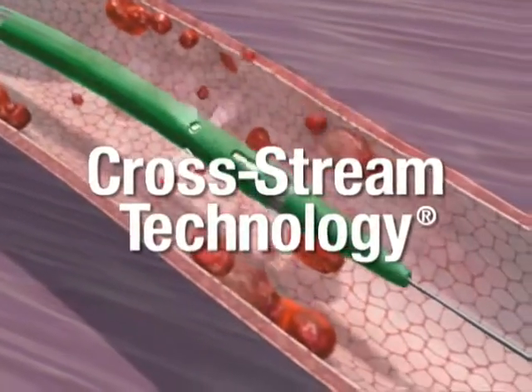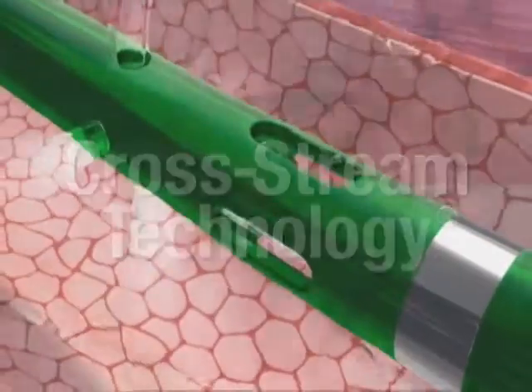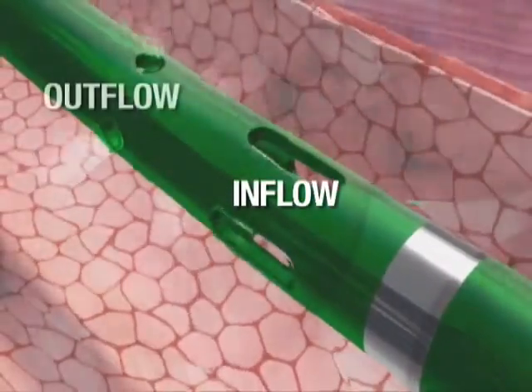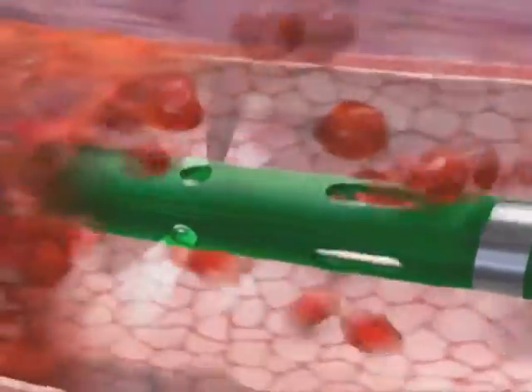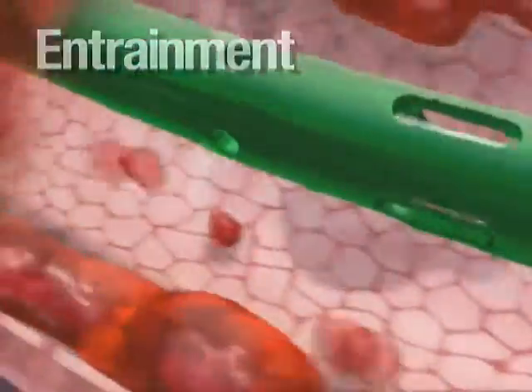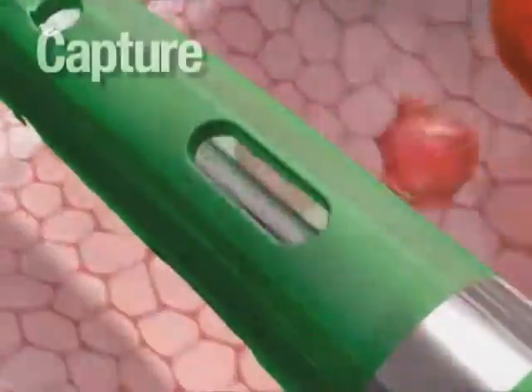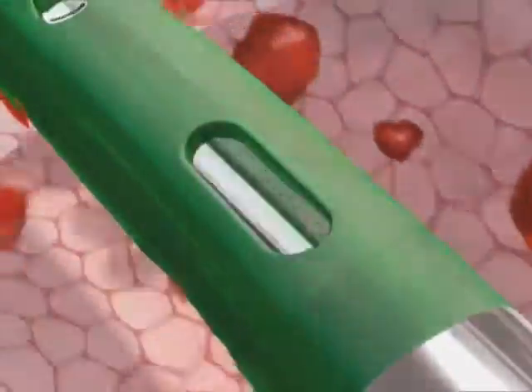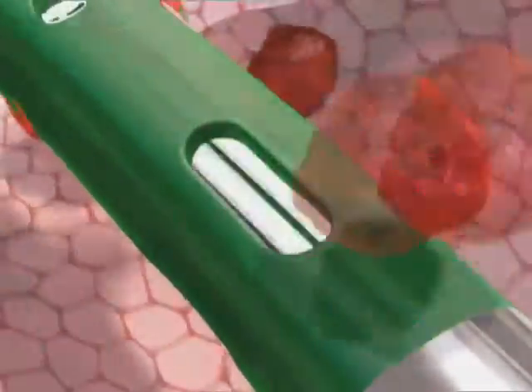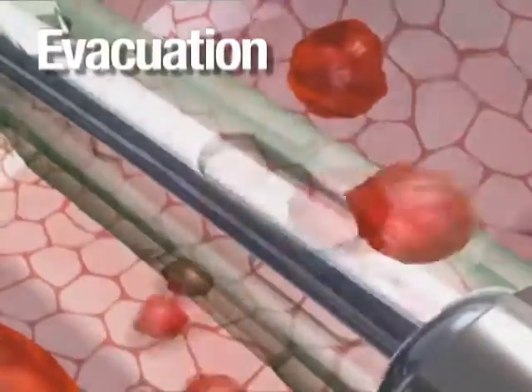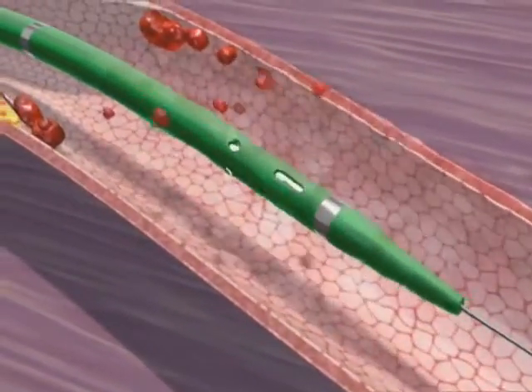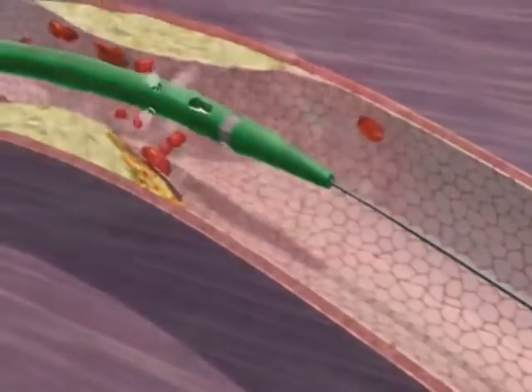Cross-stream technology describes the complex network of fluid currents generated at the catheter's inflow and outflow windows. These currents loosen thrombus from the vessel wall and draw it toward the inflow windows, a process known as entrainment. Due to the Bernoulli principle, thrombus is captured within the inflow window. Once inside the catheter, thrombus is fragmented by the high-velocity jets into microscopic particles that are quickly evacuated from the body. These jets are fully enclosed by the catheter to prevent damage to the vessel walls.